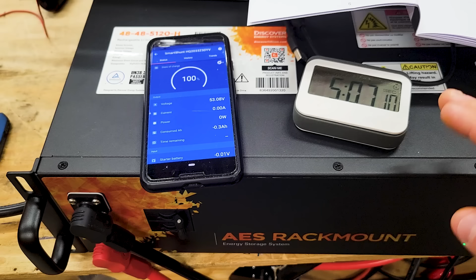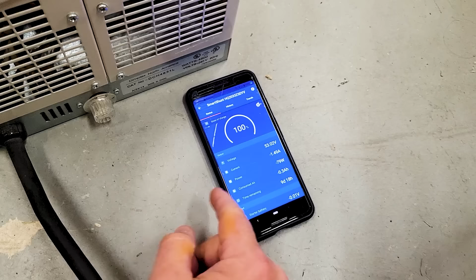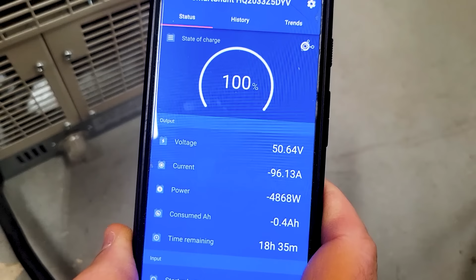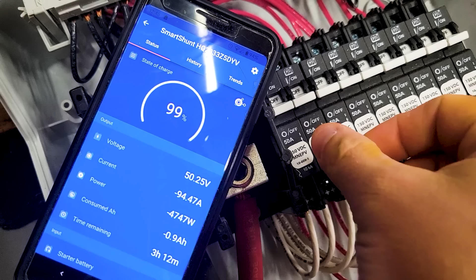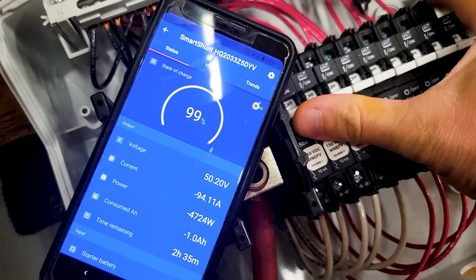So first thing we'll do is turn on the inverter, and we'll get about 95 amps, I think it was, with just the inverter, and then we'll go over to the water tank. All right, so we got our 240 volts. So now we'll come over here and turn on the space heater. We've got about 95 amps on that. Now that the inverter is running, we're going to turn on these 3 circuit breakers, which should be another 100 amps on the battery. And we'll try to do this in real time.